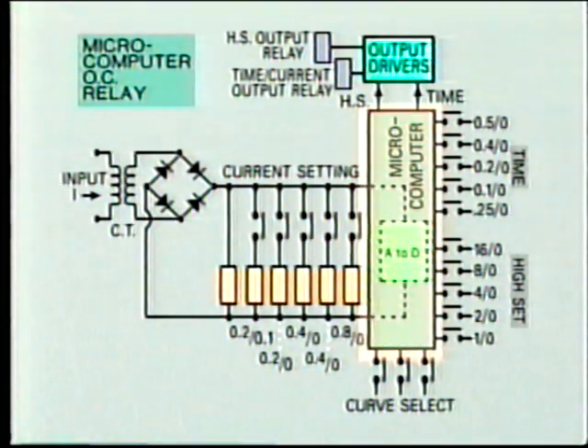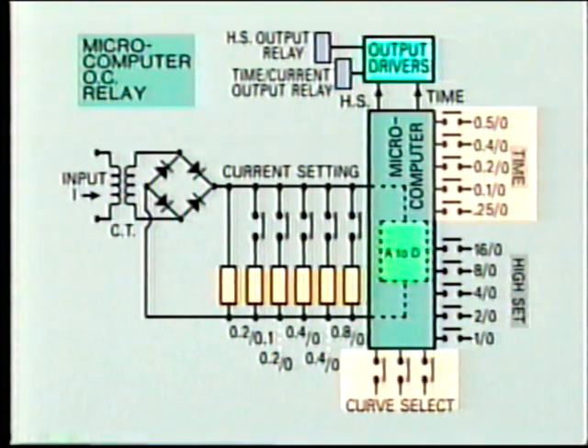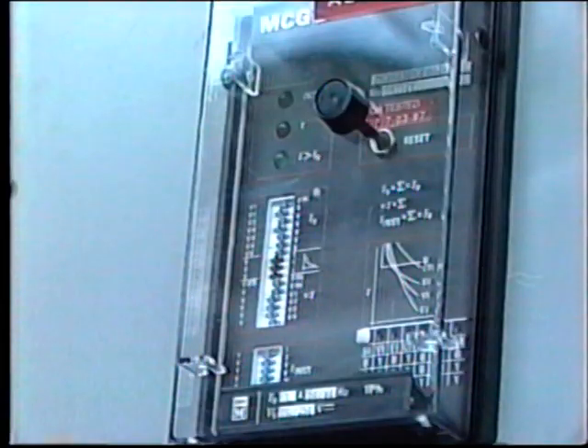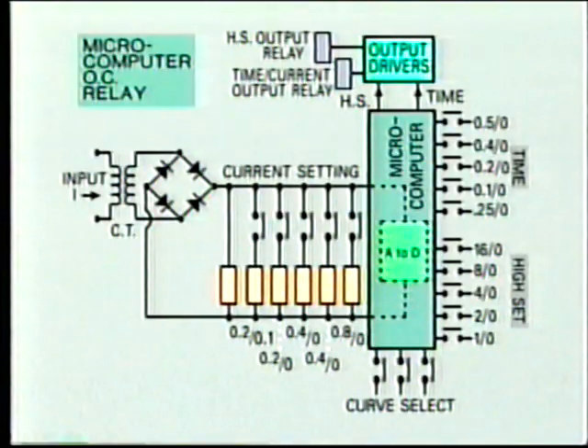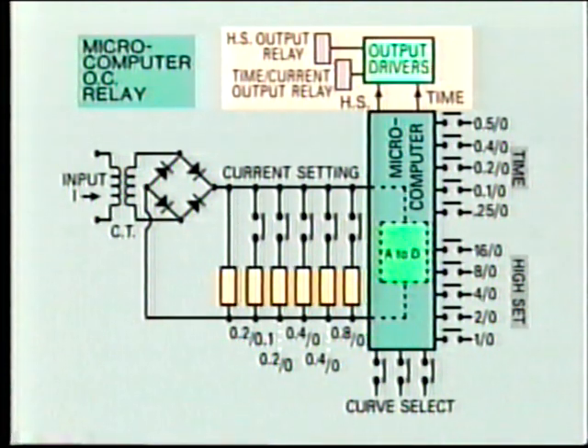The microprocessor includes analog to digital conversion, plus the relay signal processing. For setting the instantaneous overcurrent operation, the high set switches are adjusted. For the time overcurrent function, both the characteristic curve and time can be selected by switches. All of these adjustments are carried out at the front of the relay panel. The output from the relay is low-powered, so it's set up to switch an electromechanical relay, which in turn provides switching power.